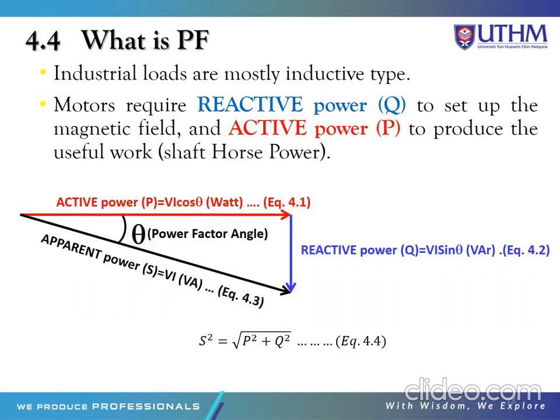Okay, next we go to subtopic 4.4, about power factor. What is power factor, PF? Industrial loads are mostly inductive type, and motors require reactive power Q to set up the magnetic field, and active power P to produce the useful work, the shaft horsepower. This is the power diagram.